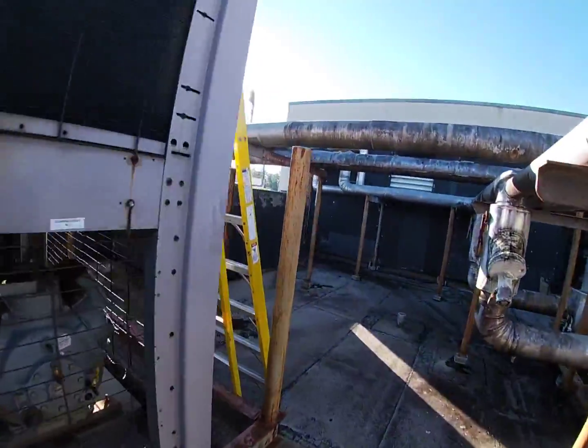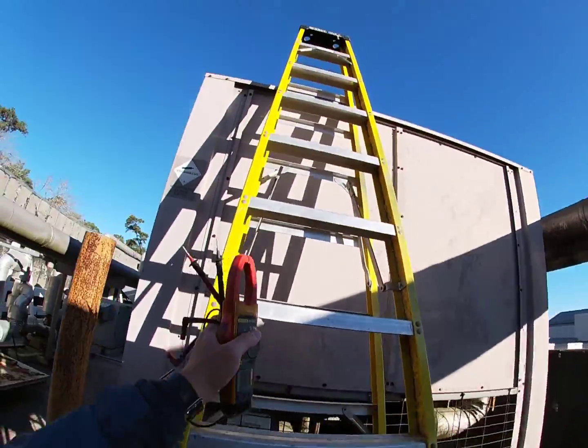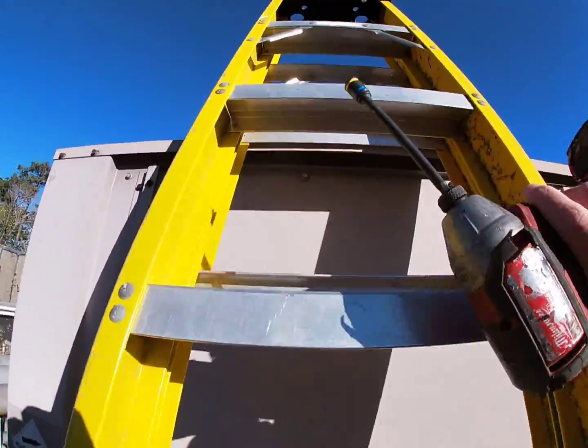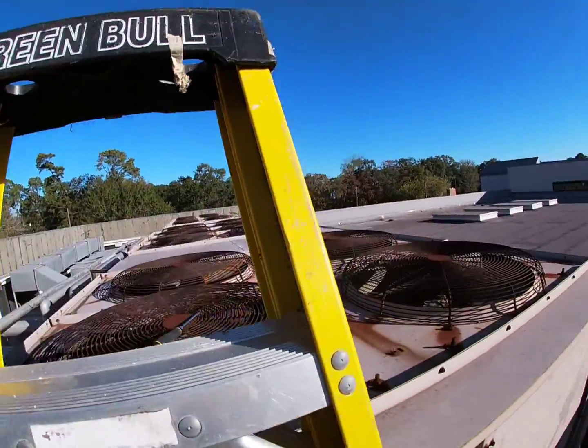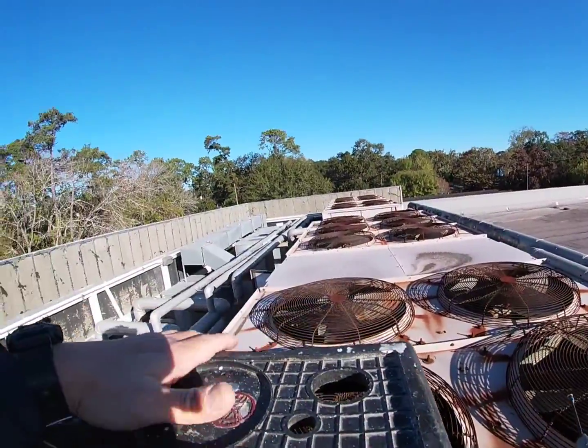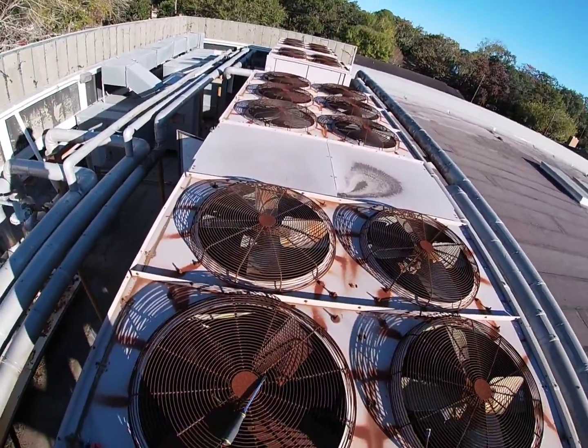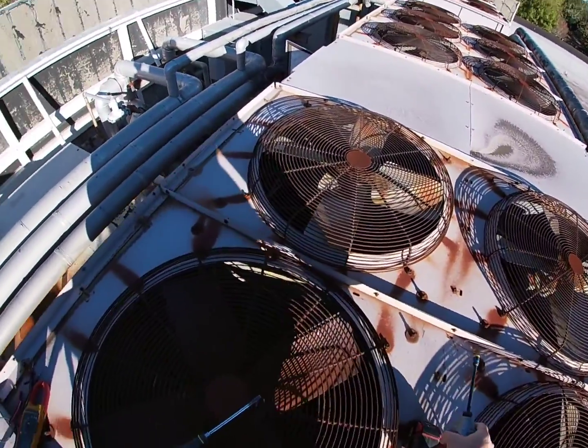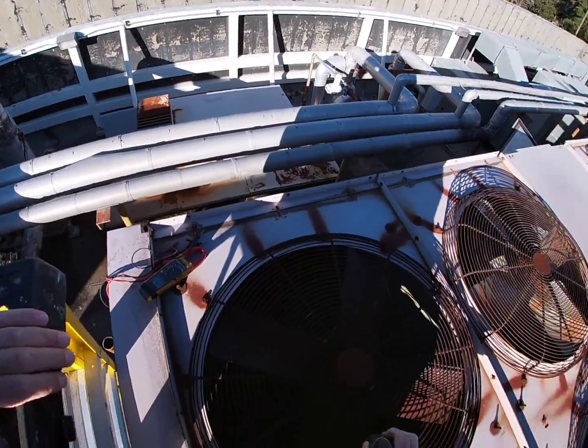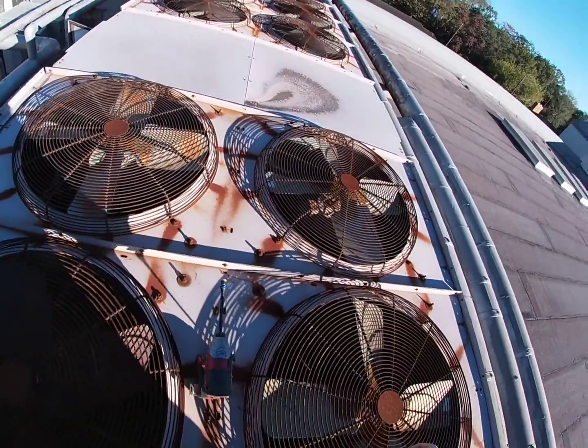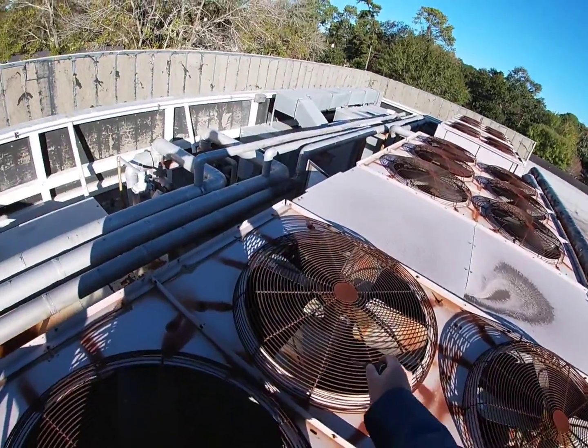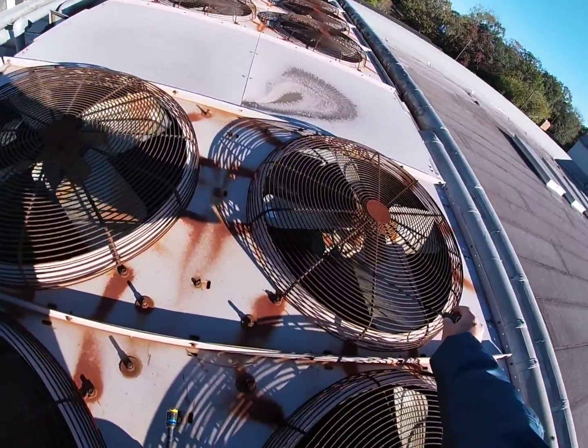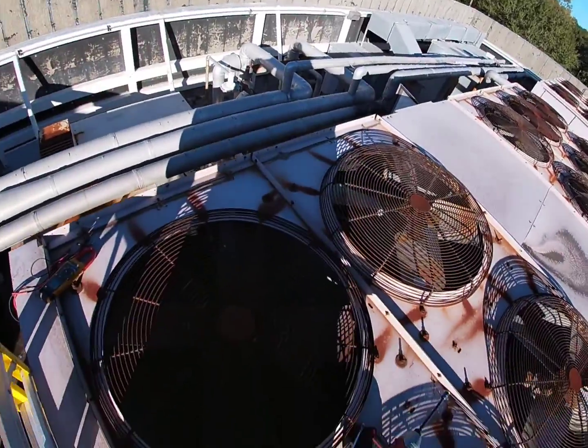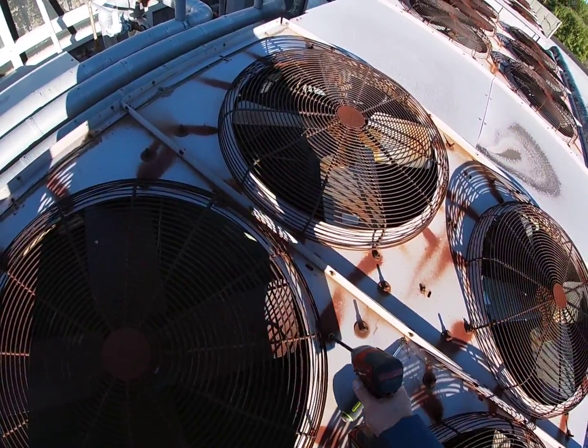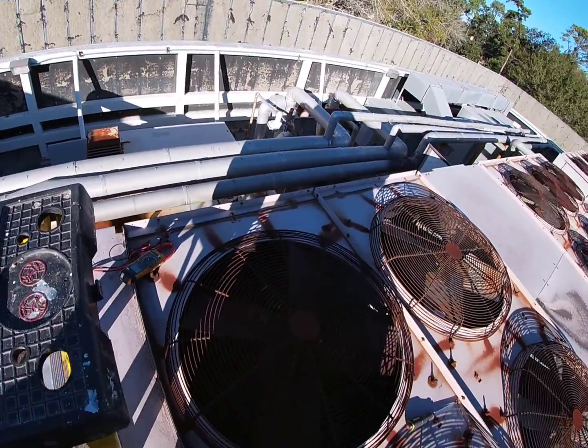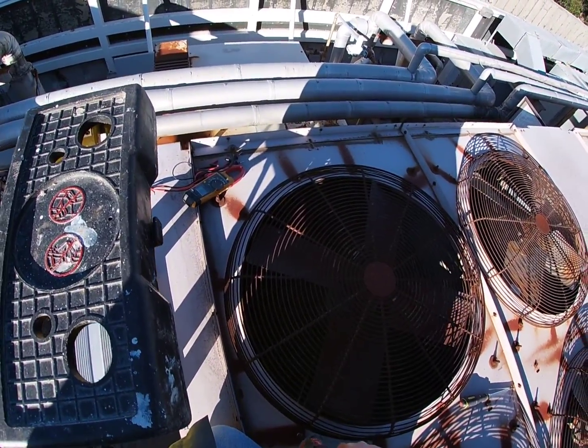Let's take a look at this condenser fan motor here. We just want to make sure it's not an issue with the wire and that it is truly the condenser fan motor here. I already have my screwdriver up here, so let's try to spin this one. That one spins, that one spins, that one spins, and then we'll go over there if this isn't the motor here. So let's go ahead and take these nuts off this motor.